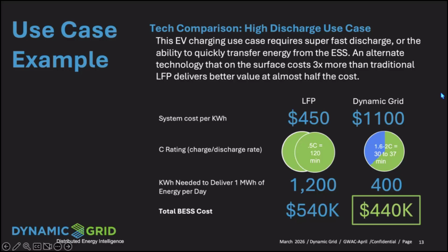Here's an EV case with a constrained interconnection. They're required to have 4 DC fast chargers, and the design called for a 1.2 megawatt hour lithium iron phosphate system. We could come in and do the same performance with 400 kilowatt hours. So while we were a higher price per kilowatt hour, we were actually $100,000 cheaper overall. Unfortunately, this project didn't happen because it was a NEVI project and NEVI got cancelled.